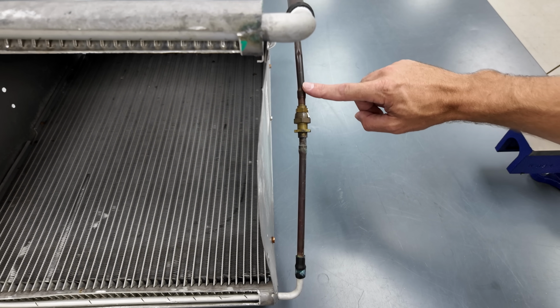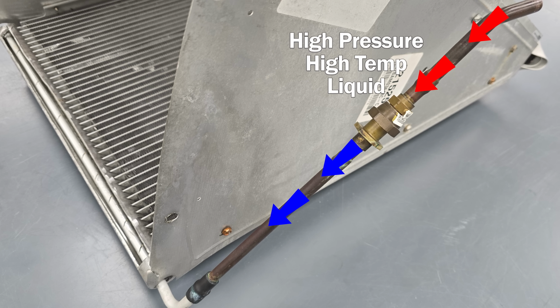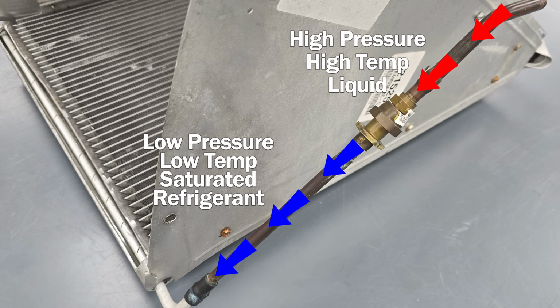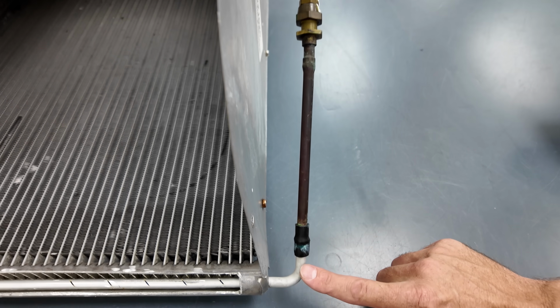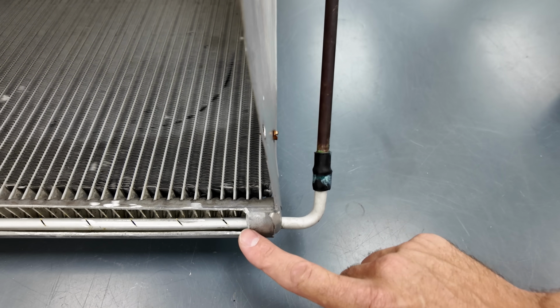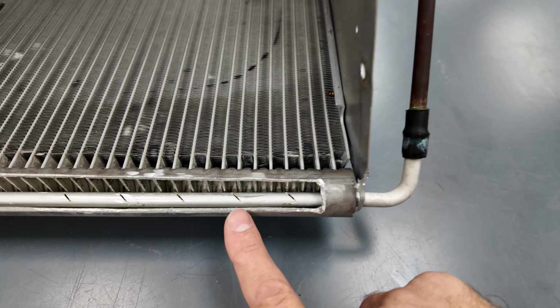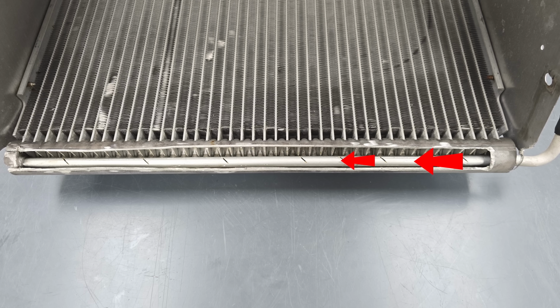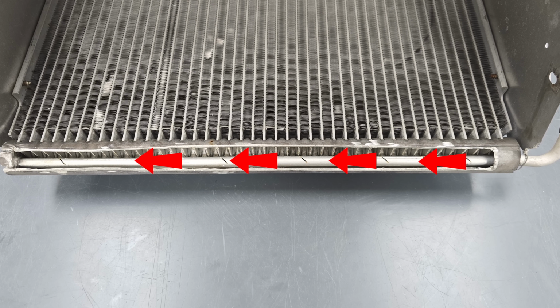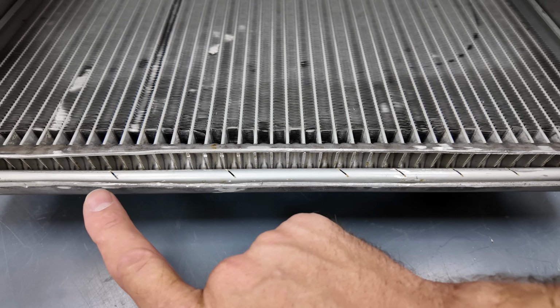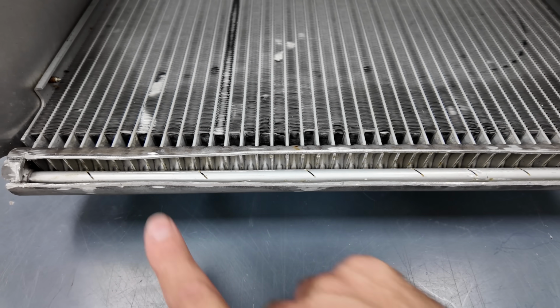To give you a tour, we have high pressure liquid entering the metering device and then low temperature saturated refrigerant exiting. So that's a mix of liquid and vapor in this tube before it enters this header section, which we cut open so that you can see it. And so that refrigerant's actually going through that little tube with all the little slits and filling the header tube before it then enters into those little channels.